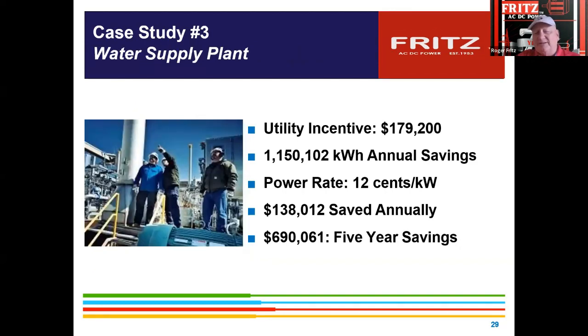This would be a water supply facility. They implemented drives and put them on several of the lift pumps and several of the booster stations. Again, they had some throttling going on, so it was about balancing the frequency, voltage, and power to the demand of the facility. And the nice thing about controls today is they have a lot of unique software in them, so you can actually pre-program those properly to run in those applications.